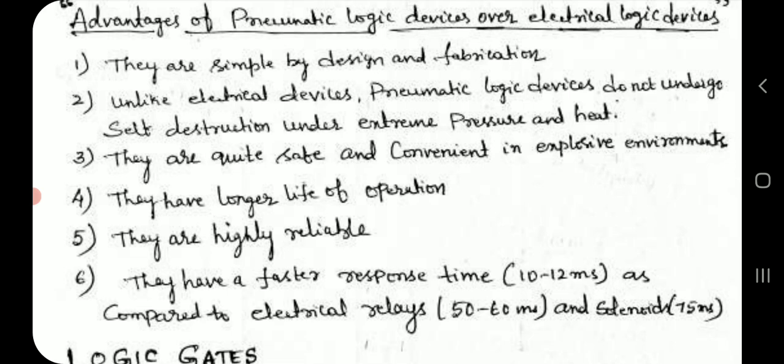Advantages of pneumatic logic devices over electrical logic devices: They are simple by design and fabrication. Unlike electric devices, pneumatic logic devices do not undergo self-destruction under extreme pressure and heat. They are quite safe and convenient in explosive environments. They have longer life of operation. They are highly reliable. They have a faster response time as compared to electrical relays and solenoids.